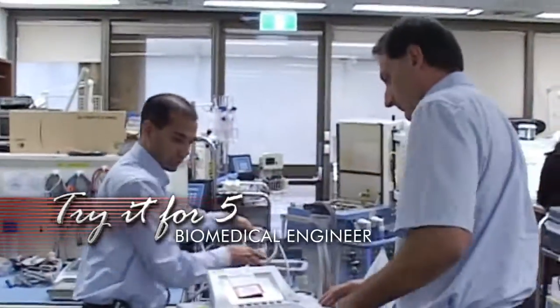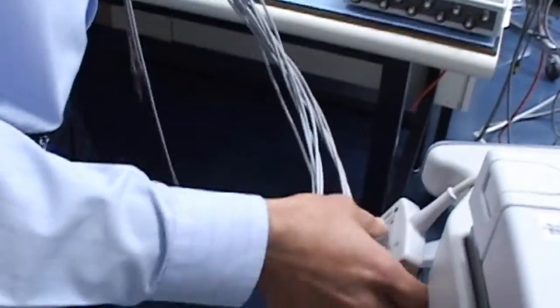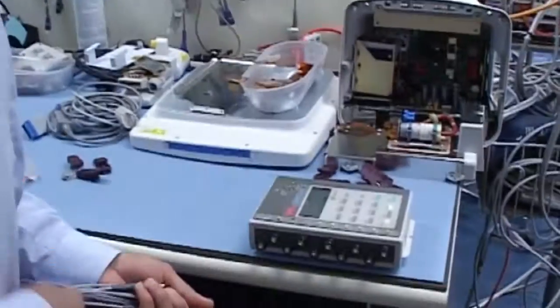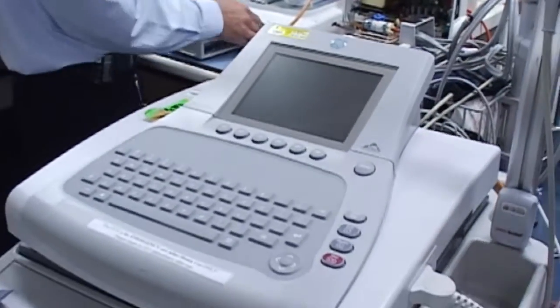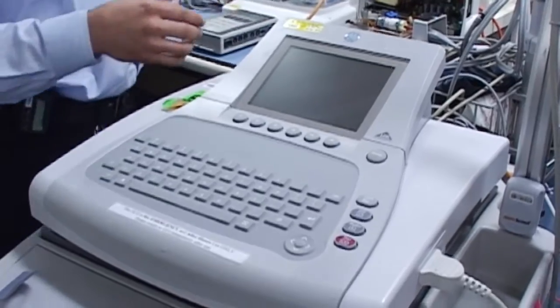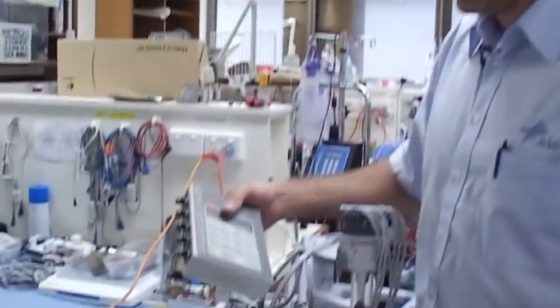Do you want to have a look at this one? It's come down from a ward saying that it's not reading correctly. It's a pretty vague description, but what we're going to do now is just put essentially a patient simulator on it. This will give us a good idea of what's actually happening with the system, if there's anything wrong with it.